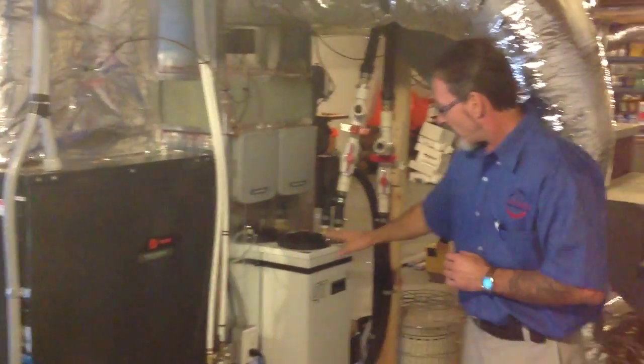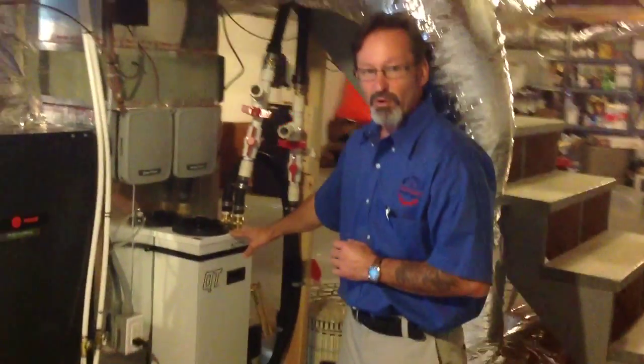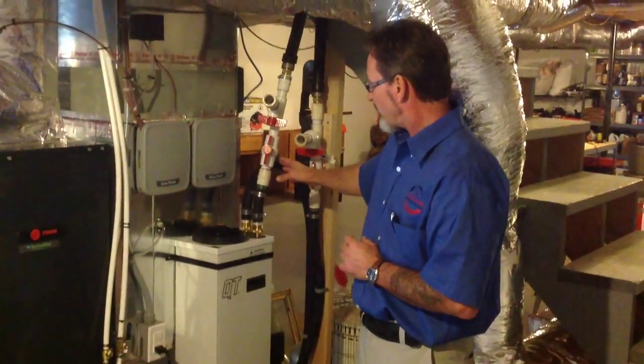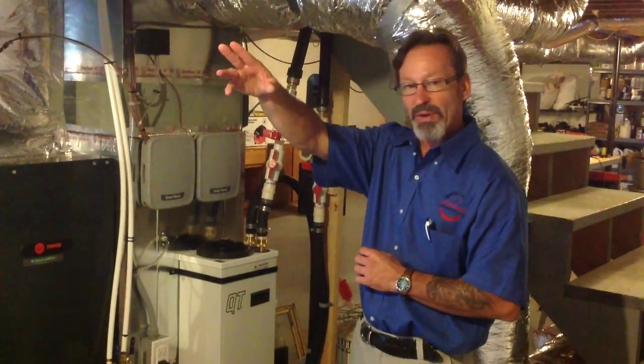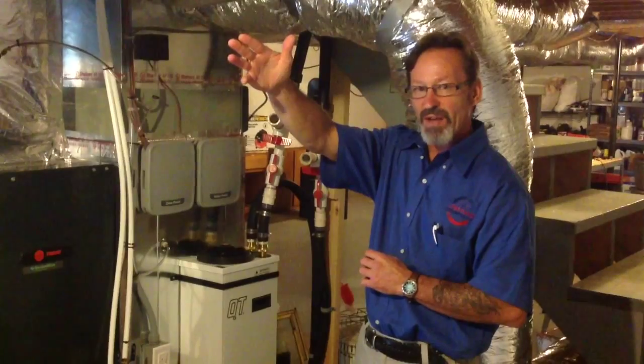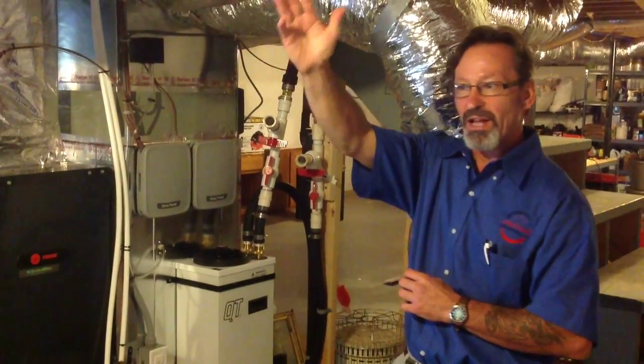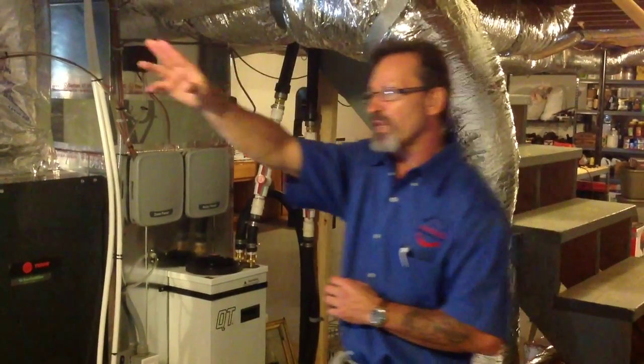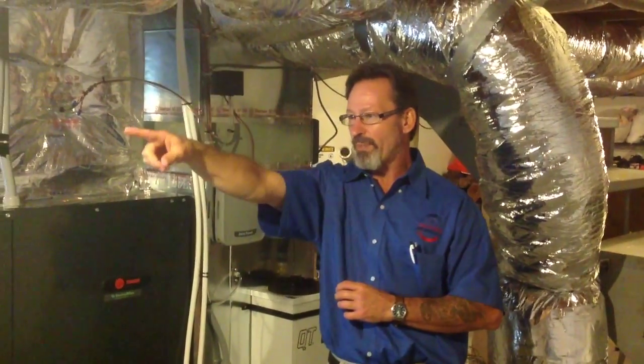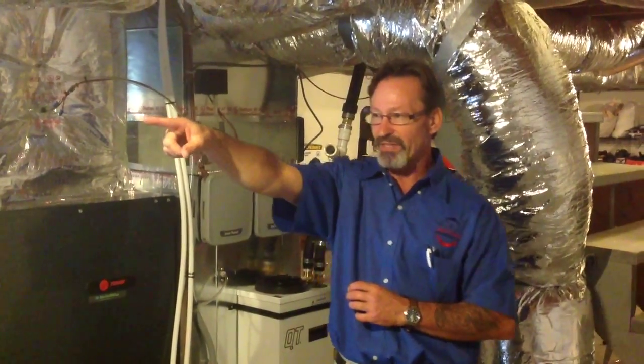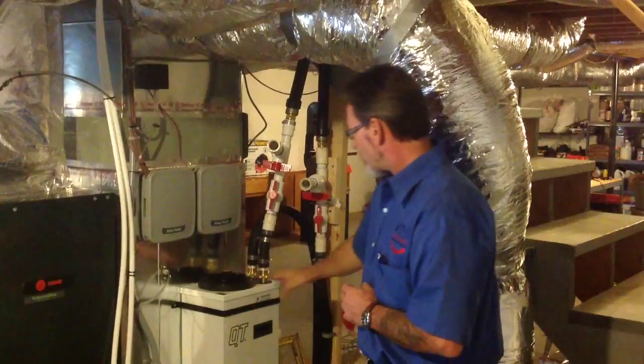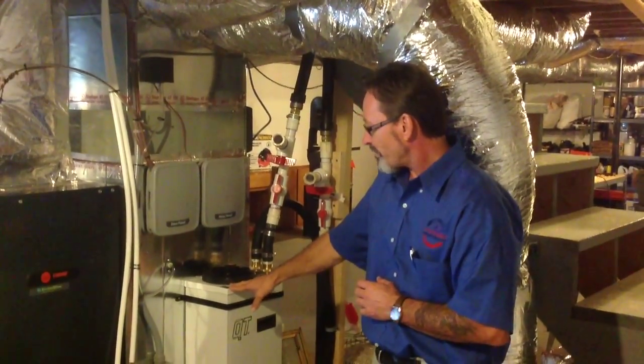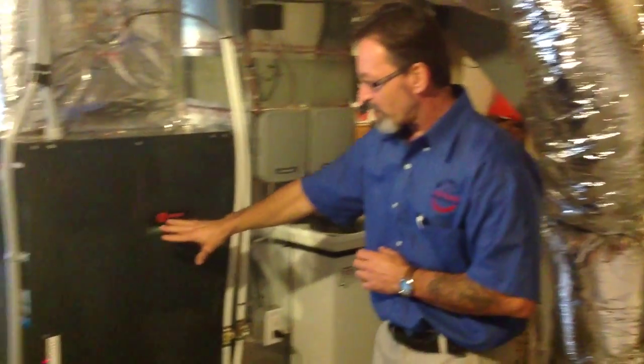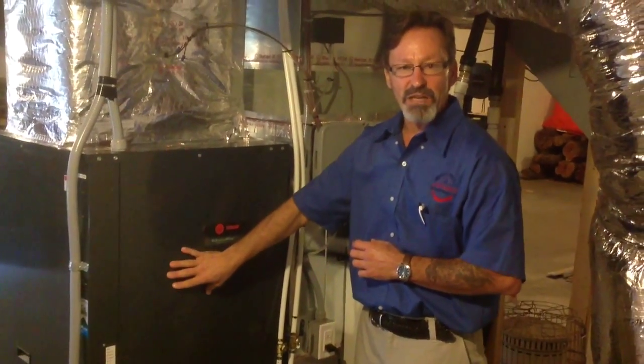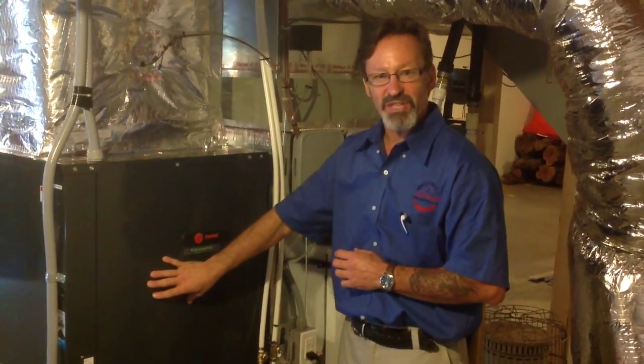Over here we've got our QT flow center, which is regulating all the water coming out. Remember, you've got 85% water, 15% ethanol out there in the horizontal field, and the pipes travel right through. We penetrated on the west end of the house, and it's tied into the QT flow center, regulating the pressure the air handler needs at the specific time of the season.